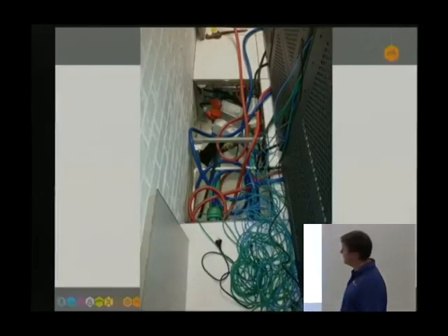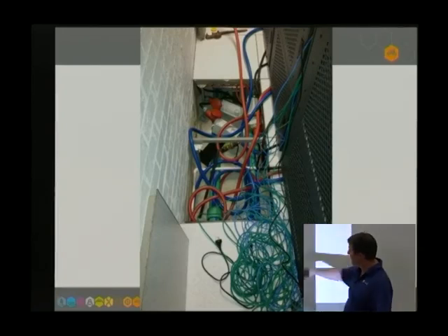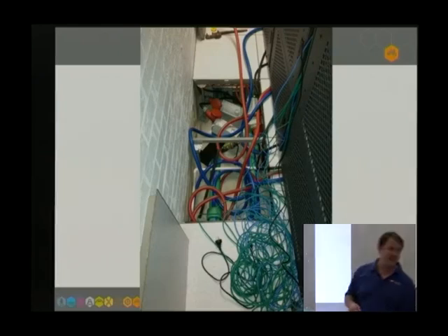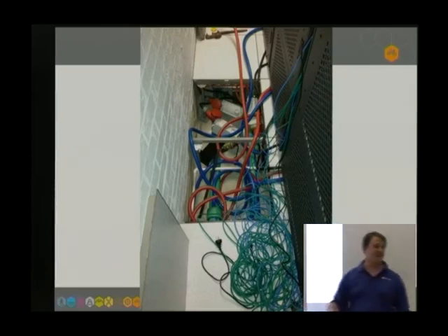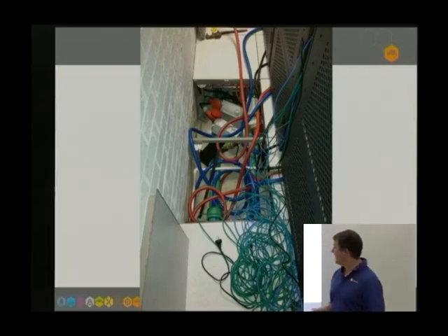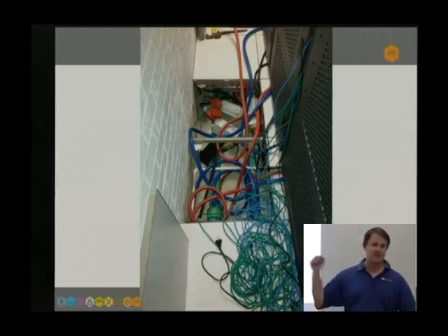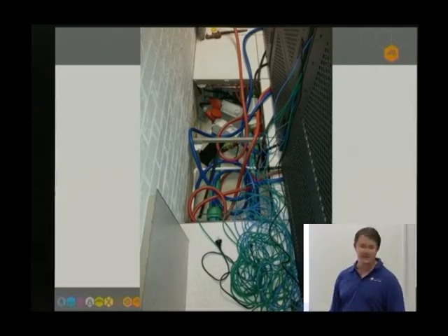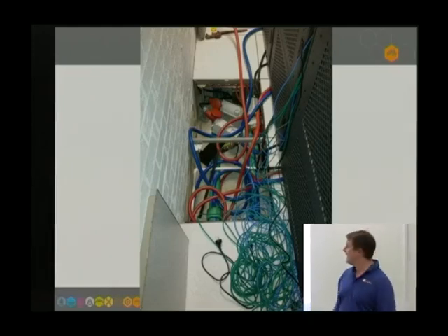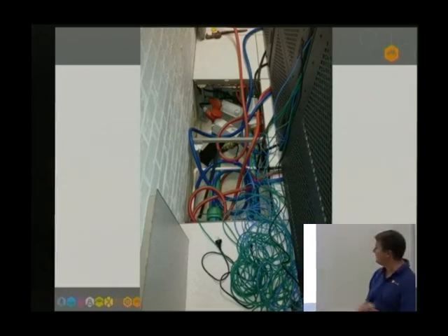Some more, so of course you start getting lots of racks, you start having lots of these water pipes, and obviously our 32 amp 3-phase power down there as well. These are big power packs, they're about so big, and their cables are quite stiff. The electricians came in and put them on all little posts all nice and neatly around the floor, but because everything was so stiff and couldn't move, I then went and unbolted everything from the floor and just had them floating loose in the bottom of the floor. Works really well now.